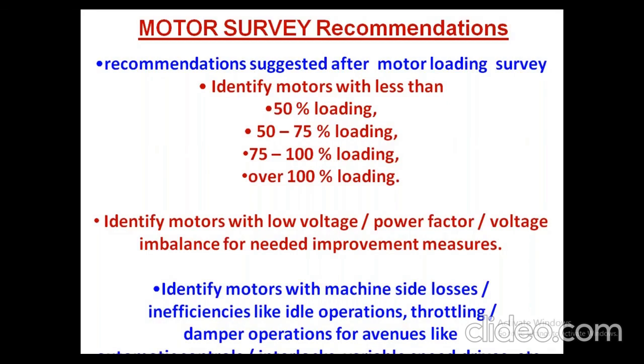If you take the energy loss happening in the motor-to-machine system, only 25% is the loss in the motor, and 75% of the loss happens on the load side. It can be machine side loss, inefficiency due to idling losses, throttling losses, damper operation. Like this, many of the losses happen only on the load side. That has to be corrected.